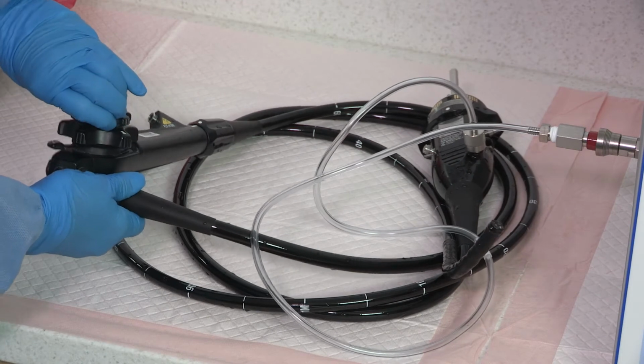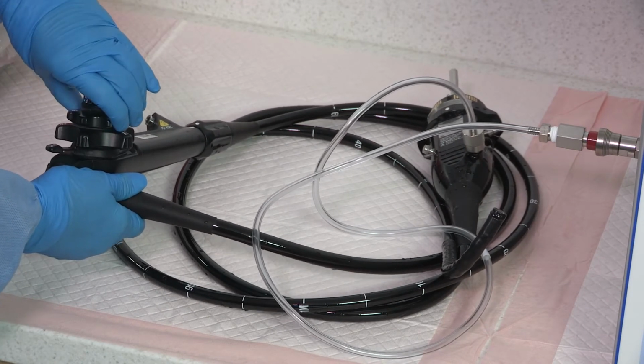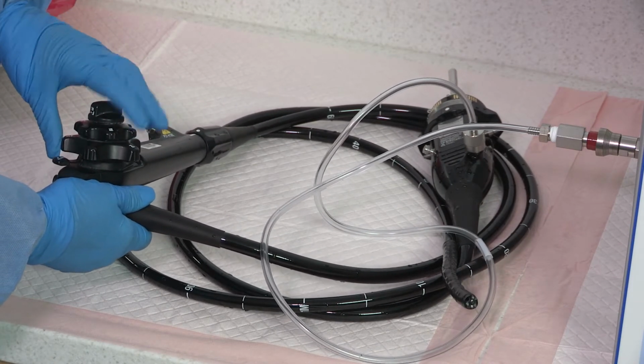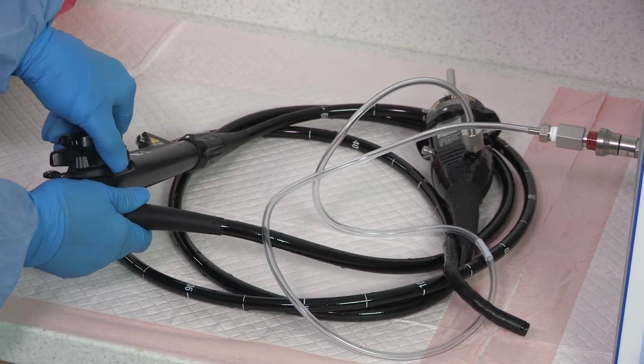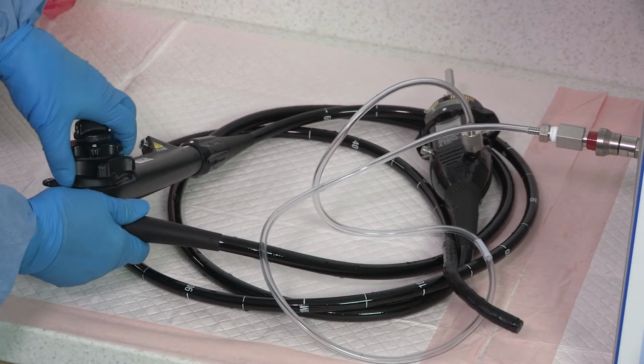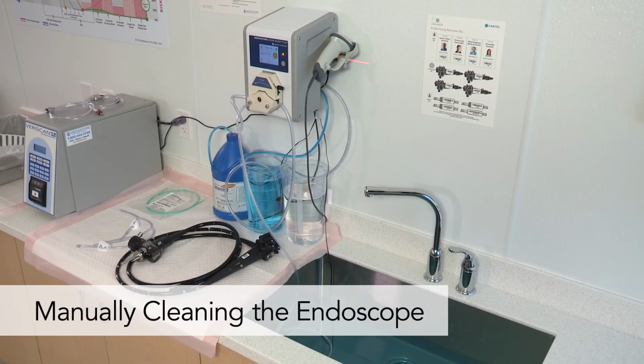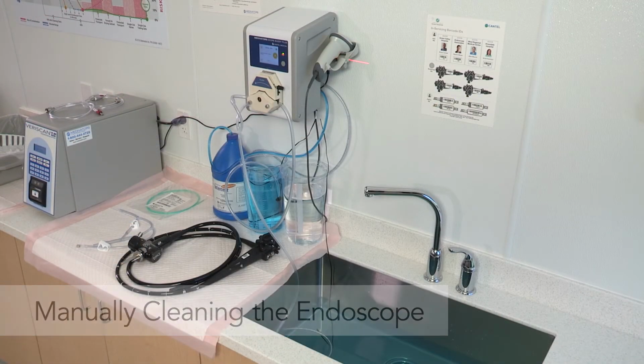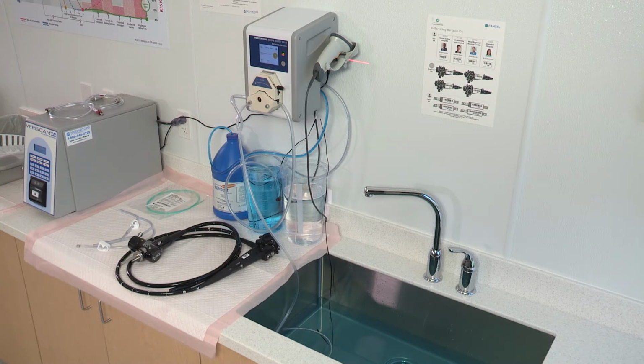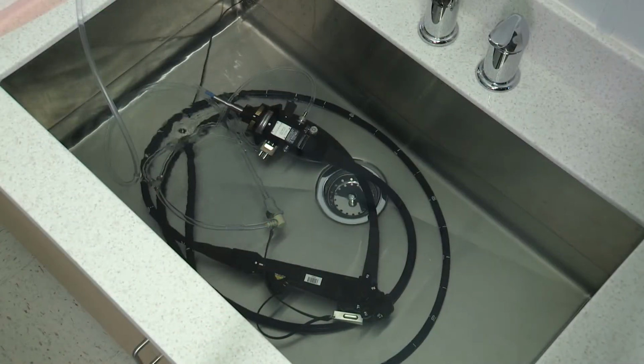The manual leak test allows for the physical turning of the control knobs to flex the bending rubber and pressing the camera switches to test these additional areas for leaks. Manually clean the endoscope by following the manufacturer's IFU. The flushing step can be done manually or automatically with the use of the Scope Buddy Plus flushing aid before disinfection in the DSD EDGE Reprocessor.